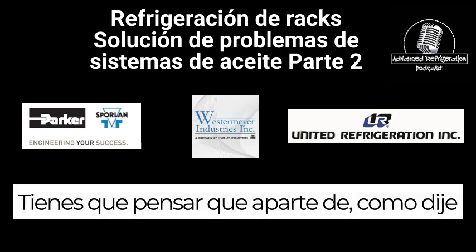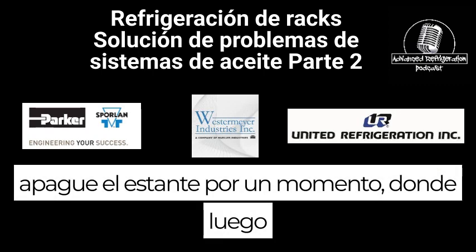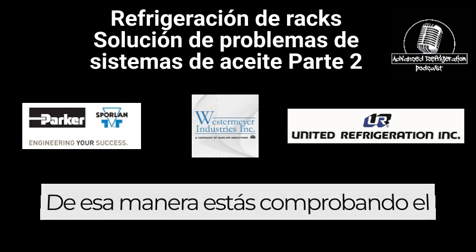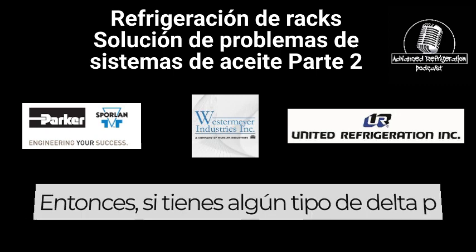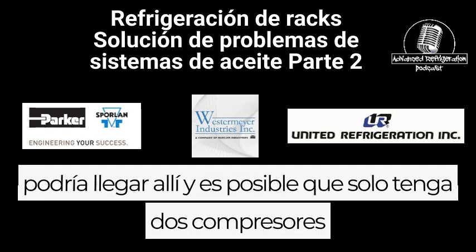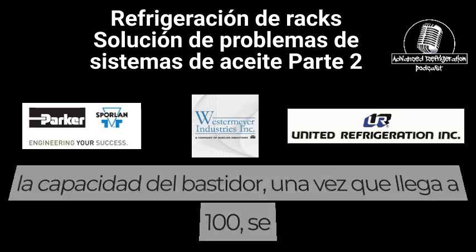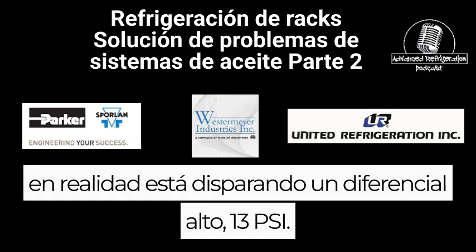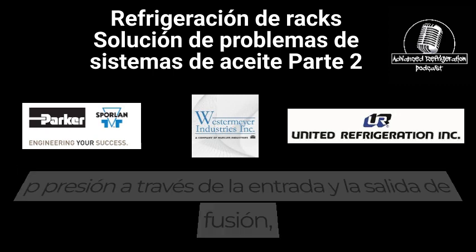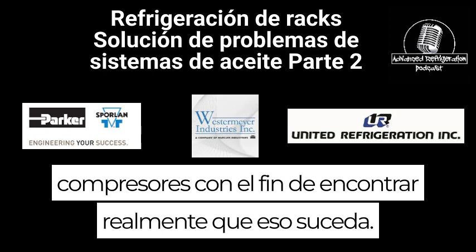You got anything to add? Other than when checking for a high differential, preferably just shut down the rack for a little bit. If you elevate your suction pressure high enough, technically all your compressors should come on. That way you're checking the full capacity of that rack. If you do have some sort of delta P gauge where it's actually intermittently going off and on, you might get there and only have two compressors running. The delta P gauge isn't going on, but then you find out by graphing that once the rack hits 100% capacity, it's actually shooting a high differential, 13 PSI. So sometimes in order to find that high delta P across the inlet and the outlet coalescing, you might in fact need to run all the compressors.